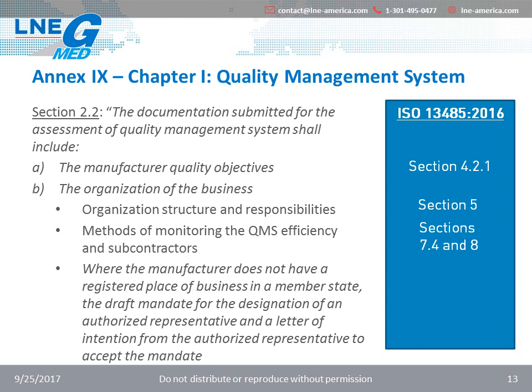Another very important element, and here I will read word for word what the regulation says in this section 2.2: where the manufacturer does not have a registered place of business in a member state, the draft mandate of the designation of an authorized representative and a letter of intention from the authorized representative to accept the mandate need to be provided. In other words, if you're a manufacturer not located in Europe, you need to have this section. But do you have it in your ISO QMS right now? No, or maybe not, because this is not covered in the ISO 13485:2016 version.